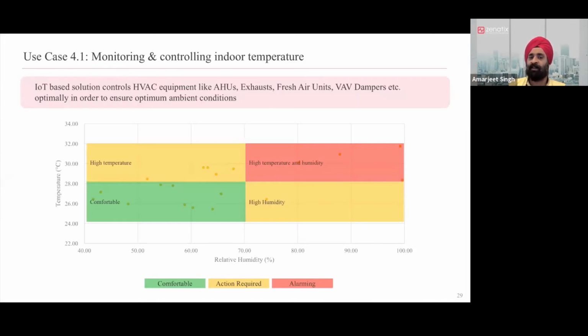Temperature - are you maintaining the right temperature or humidity for your occupants? It's a very common experience that you walk into a building and it's either too cold or too hot, never apt for your comfort level, because systems run at predefined set points. If there's a feedback loop going on, it can maintain better comfort for the occupant, and by maintaining better comfort you can reduce energy consumption. If comfort isn't maintained because certain equipment isn't performing properly, you can raise tickets and proactively service that equipment.